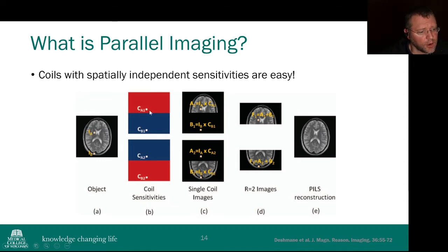Well, let's say you have an RF coil up at the front of the brain that's sensitive to exactly half the volume, and then you have another RF coil at the back that is sensitive to exactly half that head. So that front image would get you that front half of the brain, and because it's not sensitive at all to any of the signal that's in the back half of the brain, there wouldn't be anything that folds over there into the front half of the brain. And conversely, if you look at that signal coming from that coil in the back half of the brain, you'll get that signal from the back half of the brain, and that front half, again, it's all zeros because the coil is not sensitive to it, so when it folds over, you're just getting zeros on top of it.